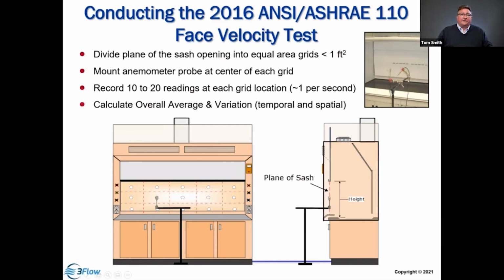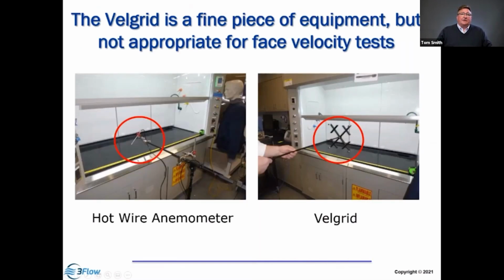So again, we're dividing into equal areas. We're going to measure velocity across the grids. Now, the anemometer that's preferred is not specified by ASHRAE 110. It does not mean that you can't use other pieces of equipment, you're just not following ASHRAE 110.